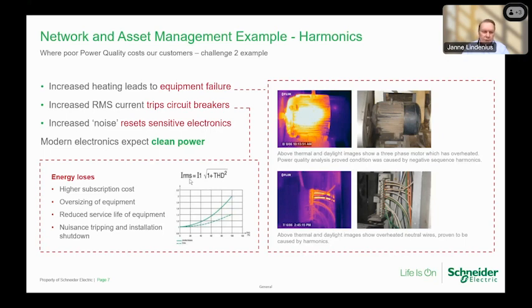Then we also need to notice the energy losses. Energy losses are directly proportional to the squared current of the transformer in the transformer coils. Increased current increases the power cost, leads to oversizing of the equipment, reduces the lifetime expectancy of the devices, and causes nuisance trips. Next slide, please.